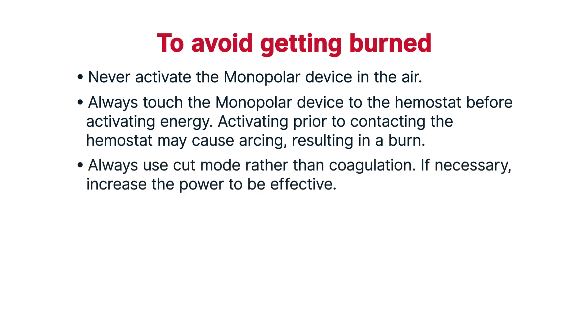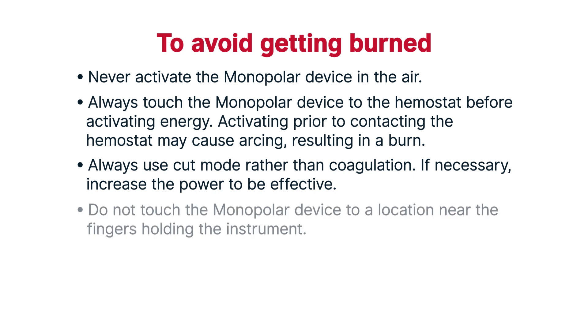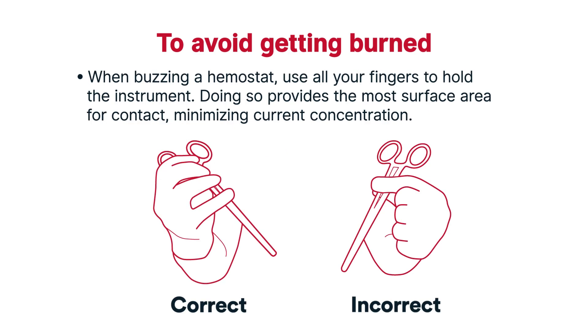To avoid getting burned: always use cut mode rather than coagulation — if necessary, increase the power to be effective. Never activate the monopolar device in the air; always touch the monopolar device to the hemostat before activating energy, as activating prior to contacting the hemostat may cause arcing, resulting in a burn. Do not touch the monopolar device to a location near the fingers holding the instrument. When buzzing a hemostat, use all your fingers to hold the instrument, as doing so provides the most surface area for contact, minimizing current concentration.